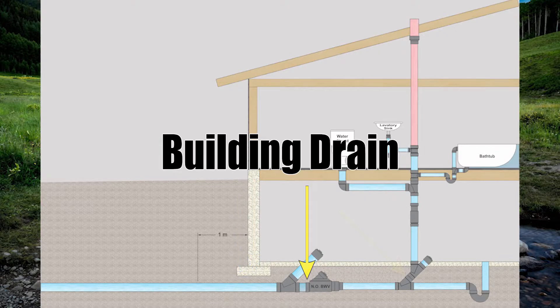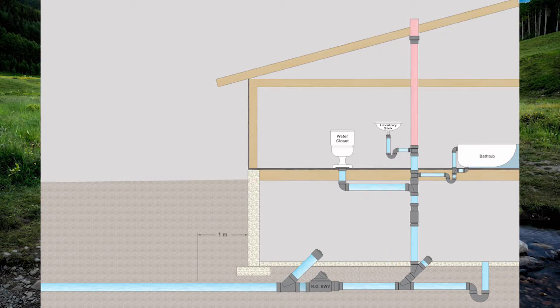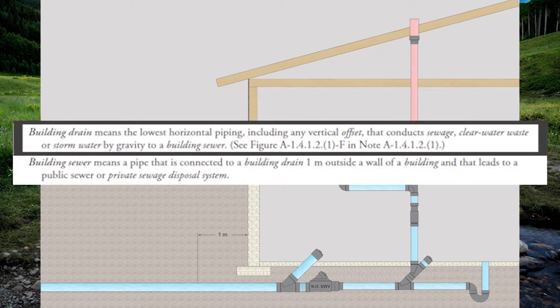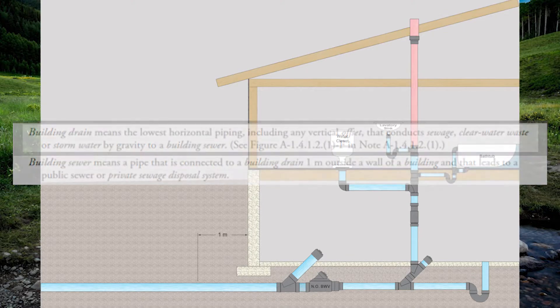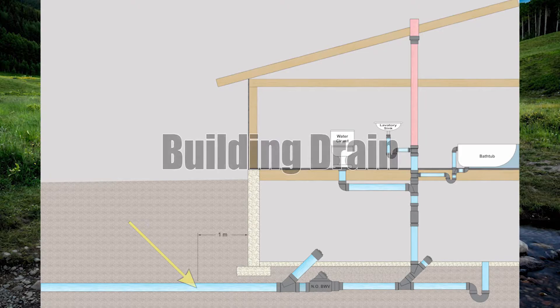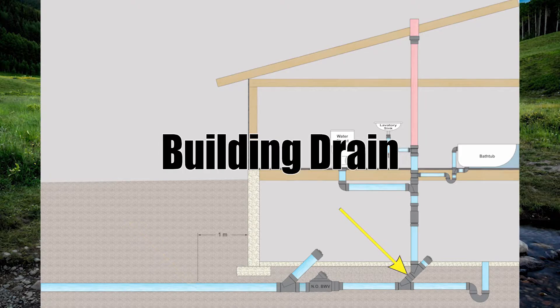At the one meter mark the building sewer ends and the building drain begins. This building drain will continue underneath the footing, through these devices, and end at the vertical pipe we call the main stack. The code definition for building drain is: the lowest horizontal piping, including any vertical offset, that conducts sewage, clear water waste, or storm water by gravity to a building sewer. In practice, it's industry standard to start at the building sewer and end at the main stack.